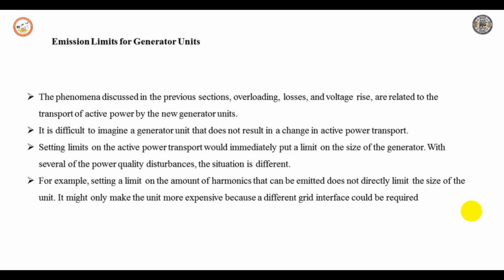The phenomena discussed in the previous sections, like overloading, losses and voltage rises, are related to the transport of active power by new generator units. It is difficult to imagine a generator unit that does not result in any change in the active power transport. Setting a limit on this active power transport would immediately put a limit on the size of the generator. With several of the power quality disturbances, the situation is different. For example, setting a limit on the amount of harmonics that can be emitted does not directly limit the size of the unit. It might only make the unit more expensive because a different grid interface could be required.